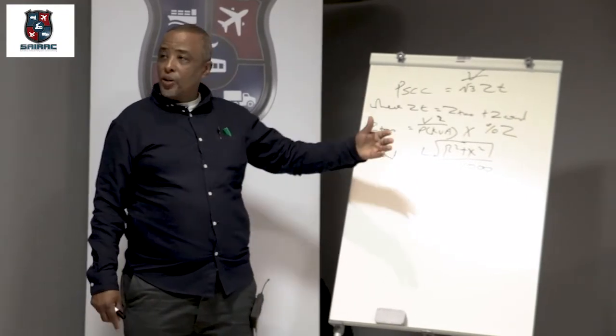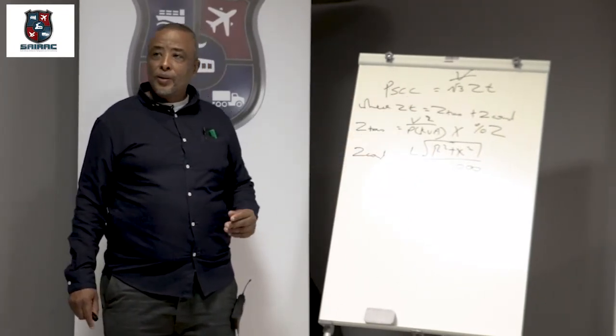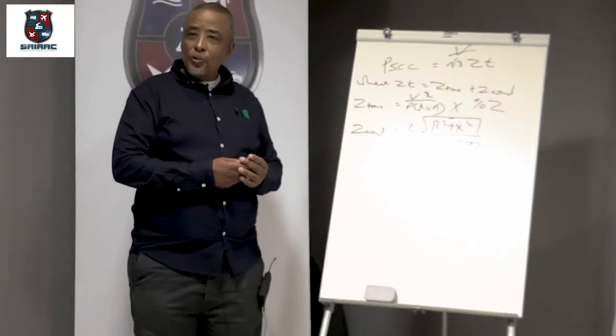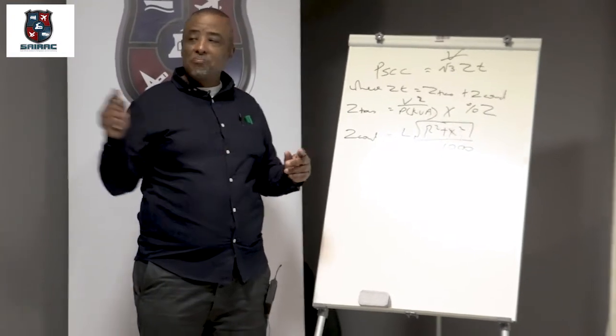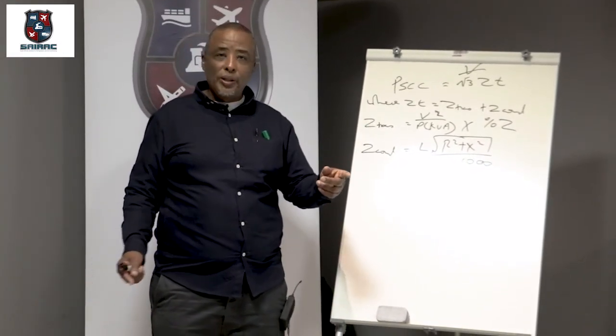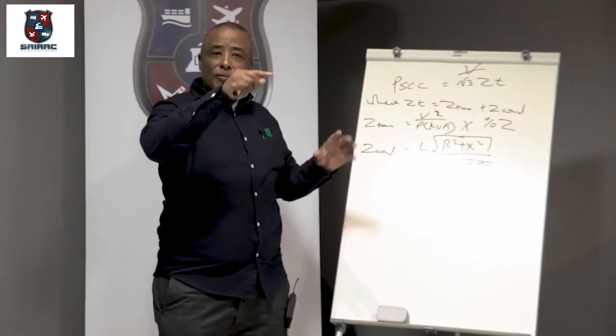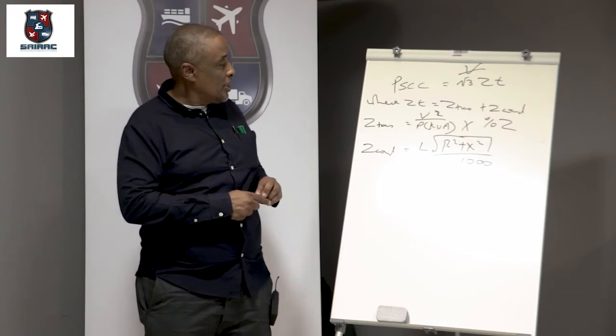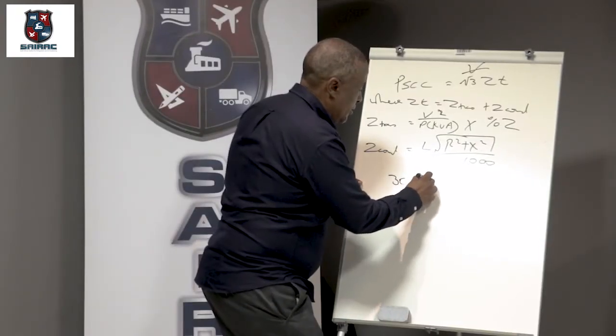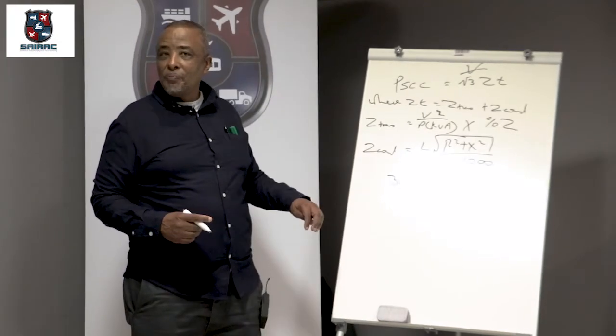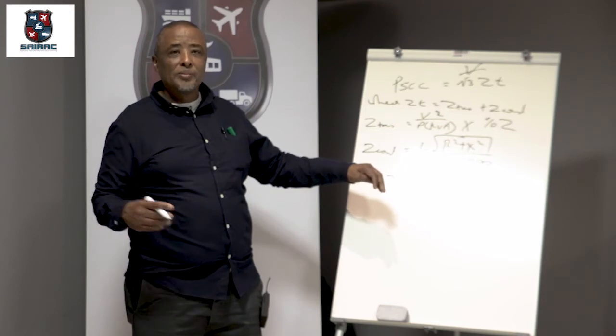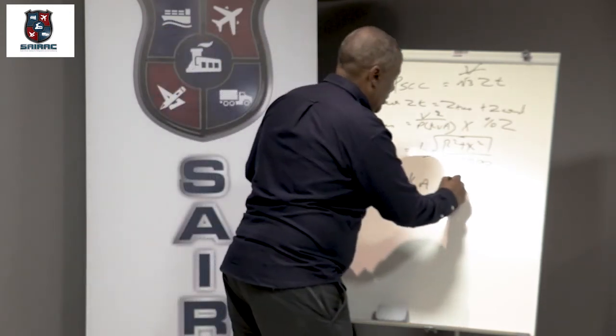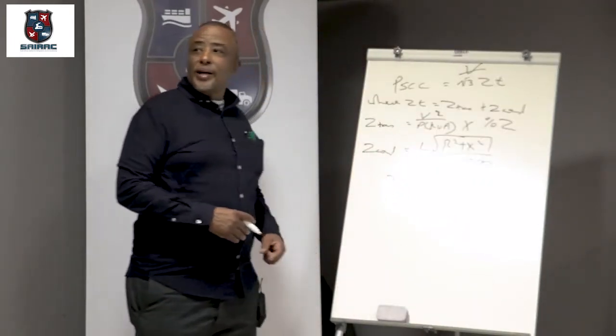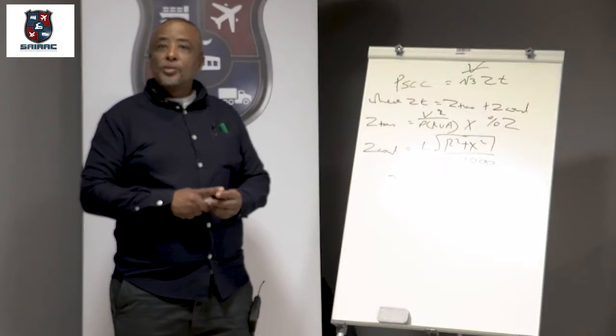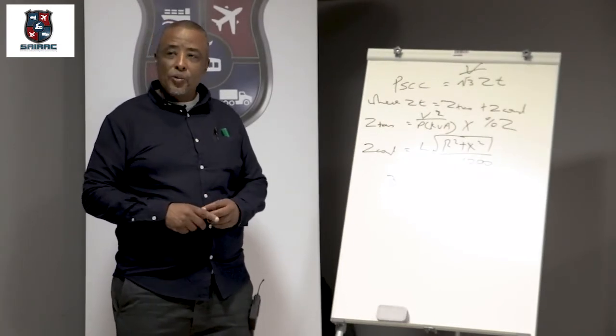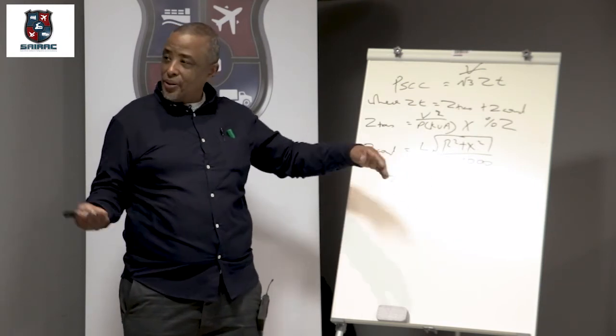Okay, cascaded system works hand in hand with PSCC. If you do maybe the first dB, like from the transformer to the first dB, or from the main dB to the first dB, you work out your PSCC is, let's say, 30 kA. I don't know prices, I'm out of touch with prices. What will a 30 kA breaker cost, roughly? Okay, let's say 10,000 Rand. And it's a massive factory. So the consultant, generally they have programs where they'll calculate, or you can calculate it, but it's going to be a bit of time.